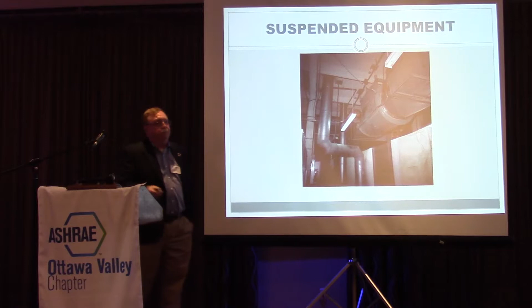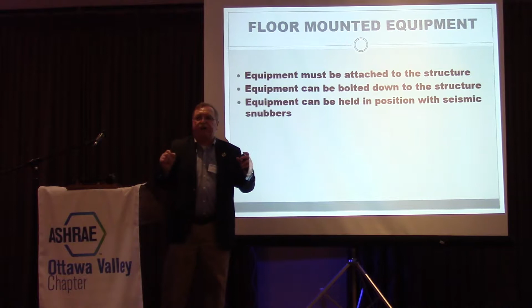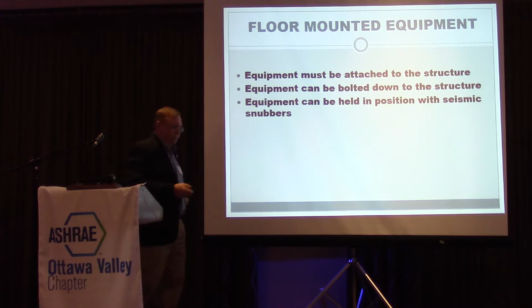Floor-mounted equipment has to be attached to the structure. The equipment must be bolted to the structure and to the equipment itself, and it's got to be held in place—if you don't have vibration isolation you can bolt it in place, or you need some kind of snubber if you're using vibration isolation, which bypasses the isolation. For day-to-day use, the seismic restraint is not in play, it doesn't work, and then as soon as the earthquake comes, it opens up, does whatever it has to do, and holds everything in place.